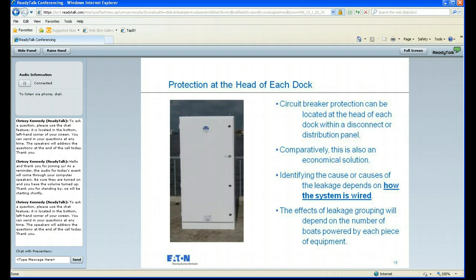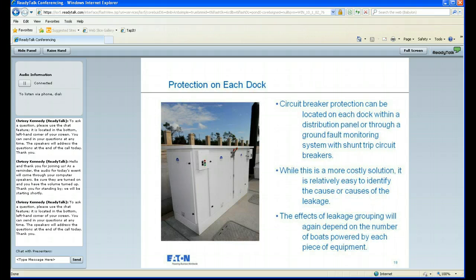The effects of leakage really depend on the number of boats being controlled by one piece of equipment. If you have multiple boats supplying small amounts of leakage into the water, you get the circuit breaker tripping quite a bit, even when some of the boats are not producing leakage high enough to make a circuit breaker trip on their own. Collectively, they are producing enough leakage into the system to cause a circuit breaker to trip or a system to shut down.